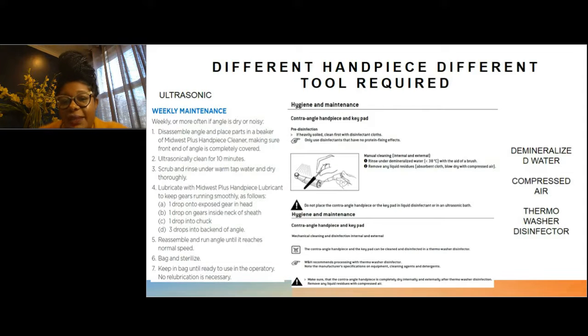So different handpieces require different tools. Okay, here are 2 different excerpts from handpiece IFUs. One states the use of an ultrasonic, and the other states the need for 3 different tools or items: demineralized water, compressed air, and a thermal washer disinfector. 2 IFUs, 4 different tools or items that are needed to reprocess them.